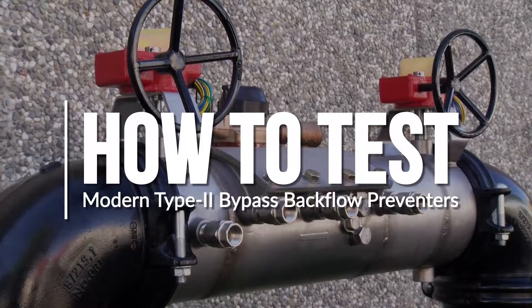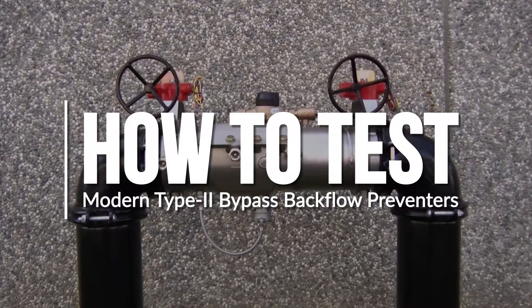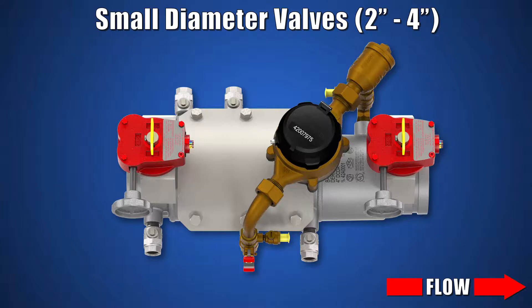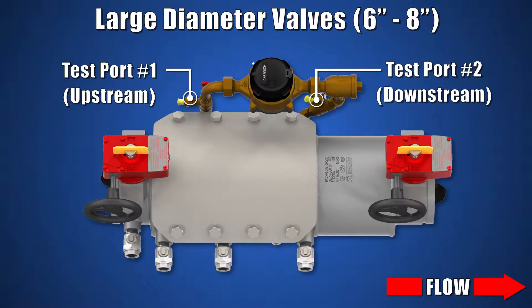The following video provides a step-by-step procedure for testing a Type 2 bypass on the Deringer 30DCDA and Deringer 50RPDA backflow preventers for USC testing. The Backflow Direct micro bypass assembly has a test port located on each shutoff valve that can be utilized for testing on the 2 through 4 inch and 6 through 8 inch Deringer 30 and 50.